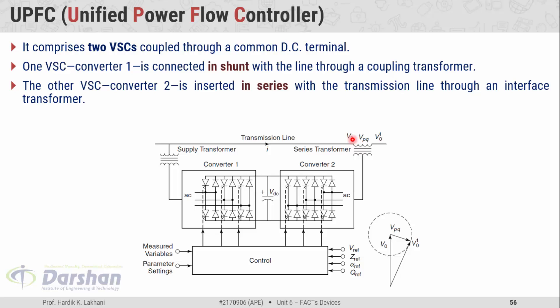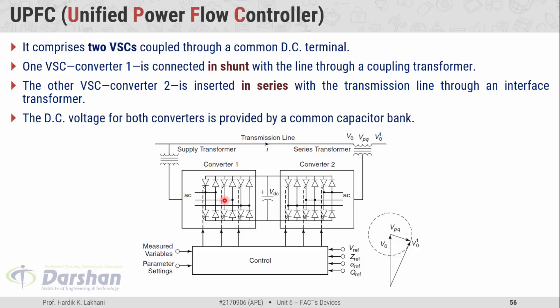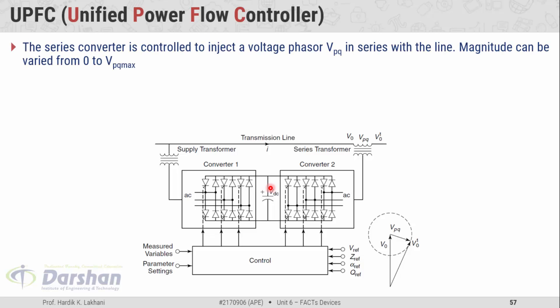You can say that the Unified Power Flow Controller is the combination of STATCOM and Static Synchronous Series Compensator — it is the combination of SSSC and STATCOM. DC voltage for both converters is provided by a common capacitor bank. The series converter is controlled to inject a voltage phasor VPQ in series with the line, and its magnitude can be varied from 0 to VPQ maximum. The injected voltage decides the exchange of real and reactive power between the compensator and the transmission line.